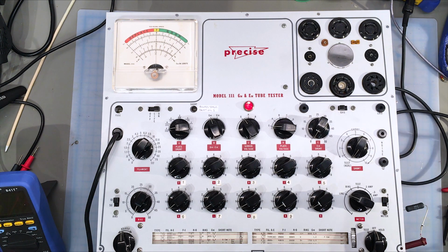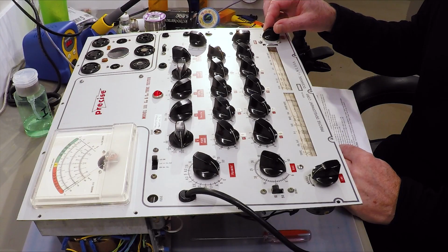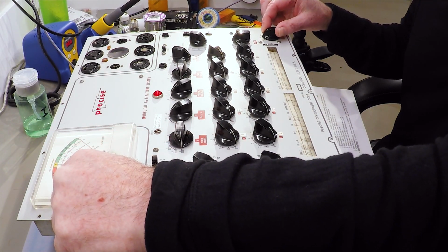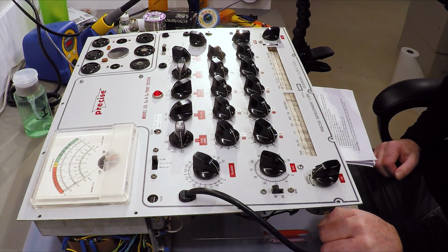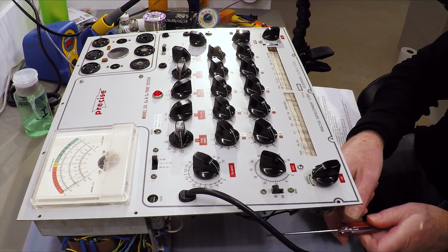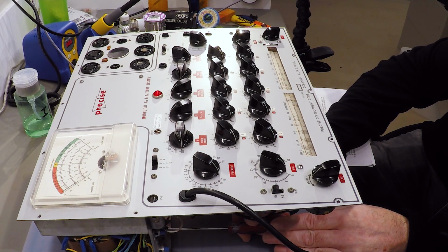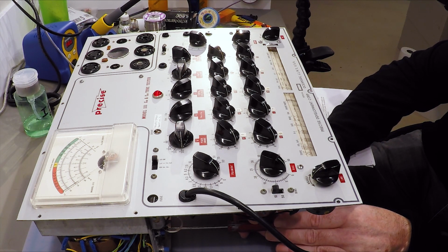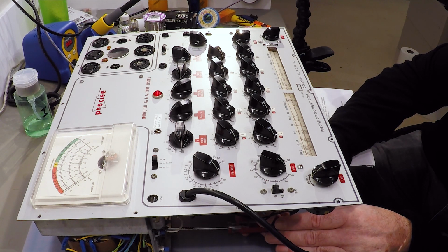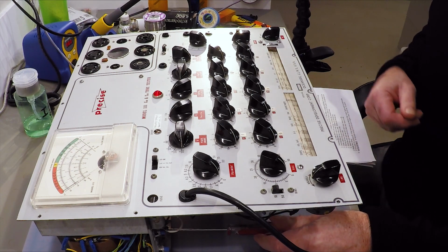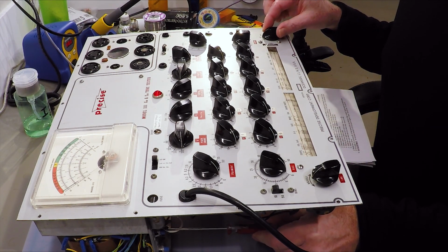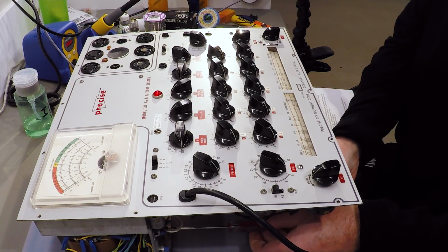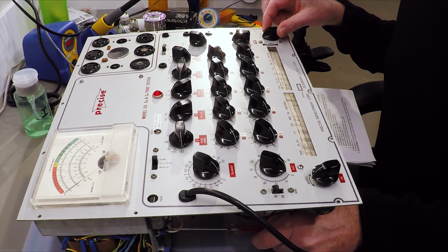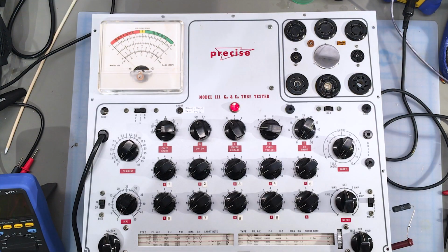And after that has been done, we're supposed to be switching the meter to test. And we see we're now at 0. And when we turn the test switch to test position, we're expecting to see a deflection from this 0 position. And we do. We see a negative deflection. And in order to adjust for this, we adjust potentiometer P4, which can be accessed from beneath the instrument. And you need either a very steady hand or a non-metallic screwdriver in order to make this adjustment. Or both, frankly. And again, we are adjusting this with a view towards minimizing, if not completely eliminating, the deflection from 0. Now we have positive deflection, negative.